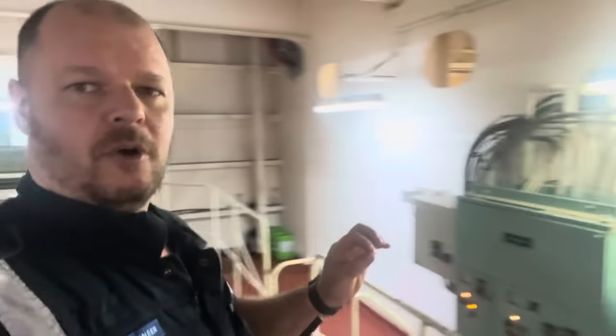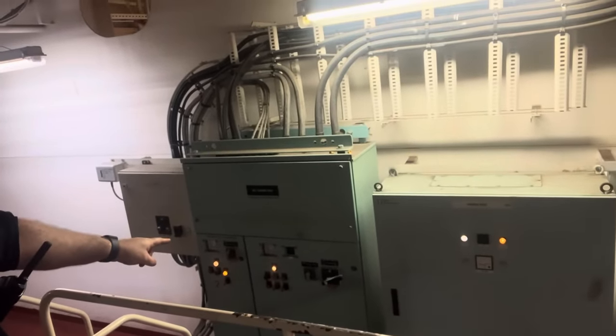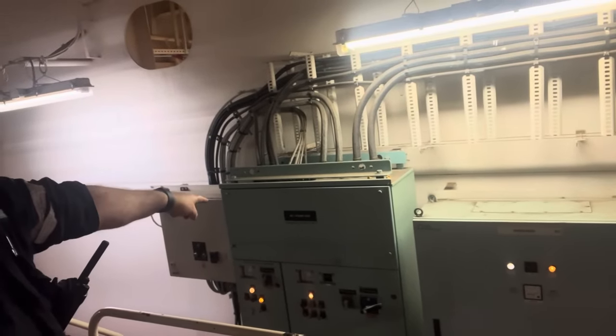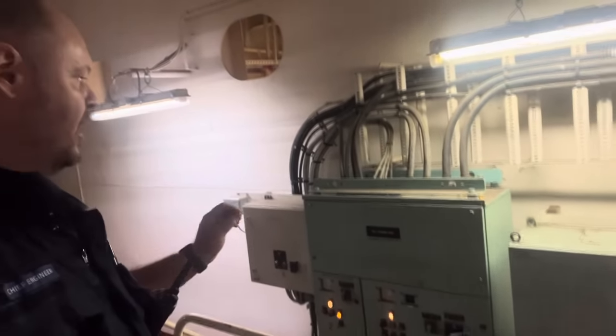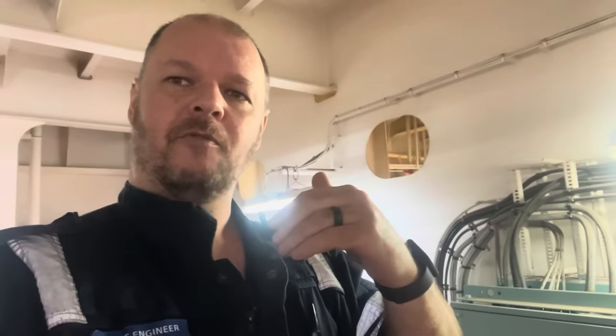The way all the controls are set up, everything is designed for failures. This is my number two pump — it's my emergency steering unit. What that means electrically is it's fed from my emergency switchboard, which is live all the time, fed from the main generators. In a blackout, the emergency diesel will start up after a certain amount of time and power the emergency switchboard — roughly 30 seconds on most ships, about 20 seconds on my ship before the lights come on and this motor can be restarted. Different regulations apply worldwide, but that's what most large ships will do.